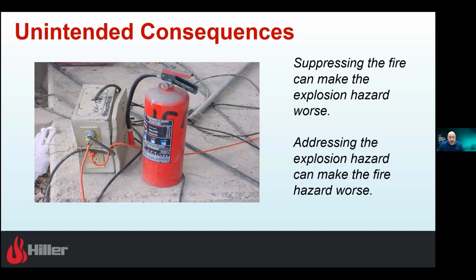We also look at mitigation measures, mitigating propagation at the module level. So we tie the cell level gas production to propagation at a module or rack level, and see what those gas productions or fire hazards may look like. An odd thing about batteries is a cell level tends to produce more gas. The module produces a little less gas because of the thermal mass, so they don't tend to propagate as much. They actually perform better, and a rack performs better than a single module, again because of that thermal mass. So those are the three main requirements we're looking at for how we manage that.